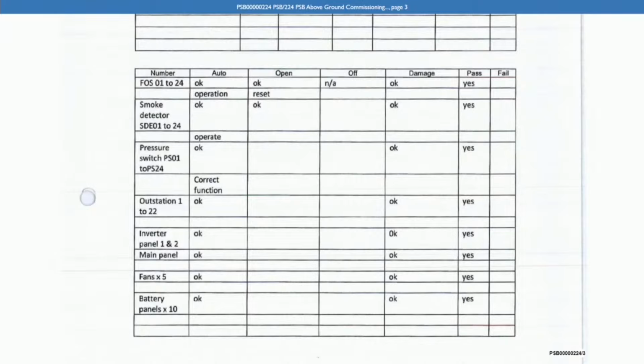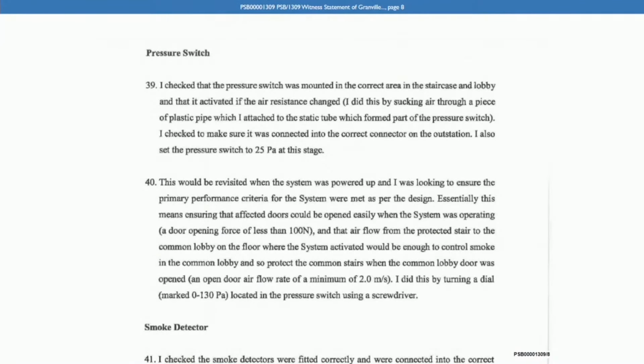Now, if we look at paragraph 39 of your witness statement on page 8, you tell us in your statement, I checked that the pressure switch was mounted in the correct area in the staircase and lobby and that it activated if the air resistance changed. I did this by sucking air through a piece of plastic pipe which I attached to the static tube which formed part of the pressure switch. I checked to make sure it was connected to the connector on the outstation. I also set the pressure switch to 25 PA at this stage. Now, do you accept that you're giving us a lot more information in your witness statement than you gave in the commissioning report?